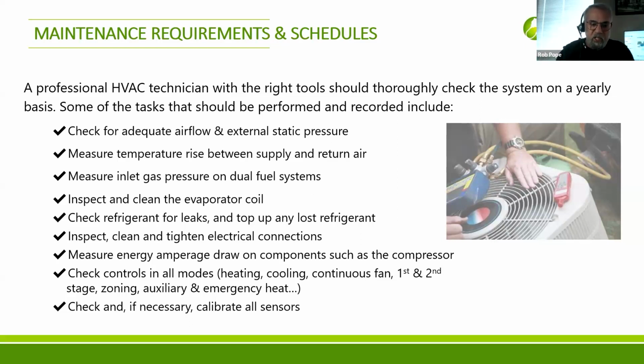So it's important to check all that, measuring the energy amperage draw on especially the compressor and the fan. Check controls in all modes. You want to check it in heating mode, cooling mode, continuous fan mode, first and second stage if there are stages, zoning if there's zoning, and auxiliary emergency heat, among other things. And check, and if necessary, calibrate the sensors.